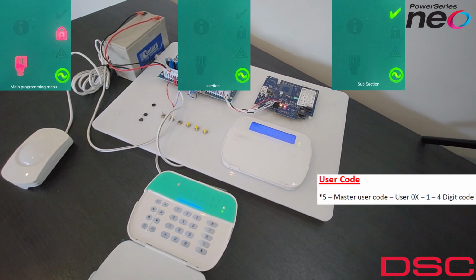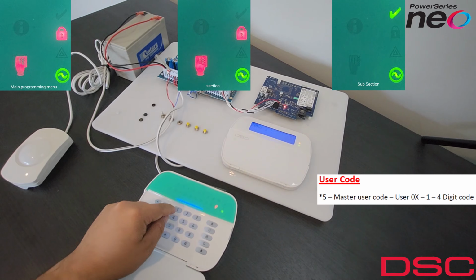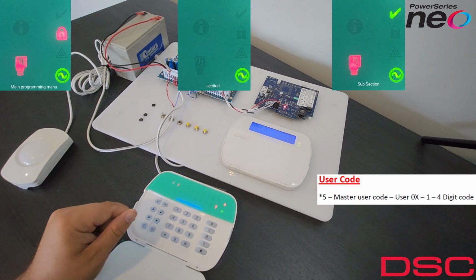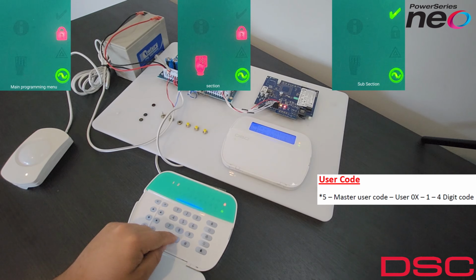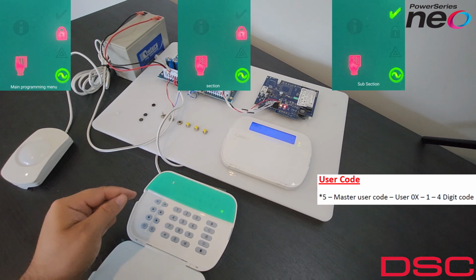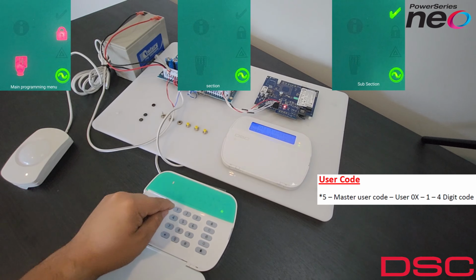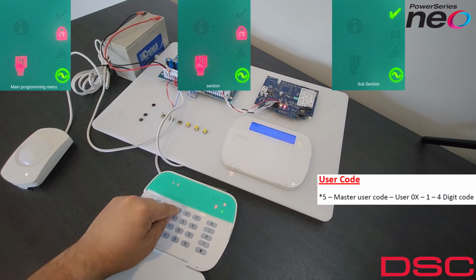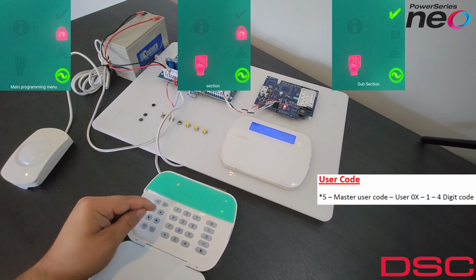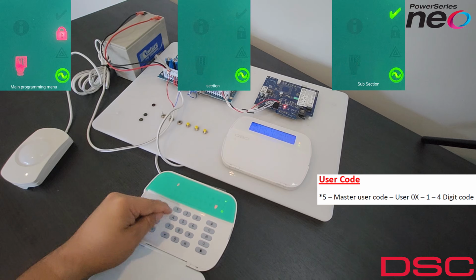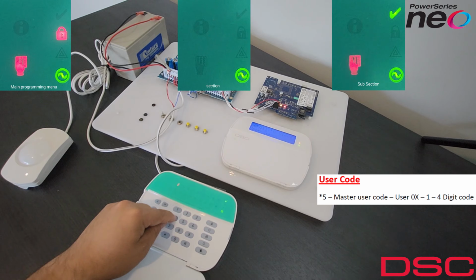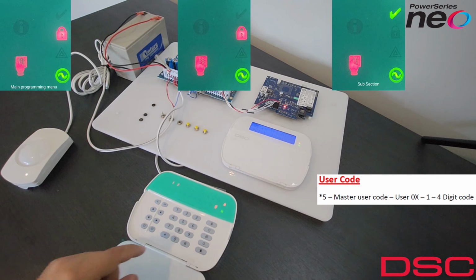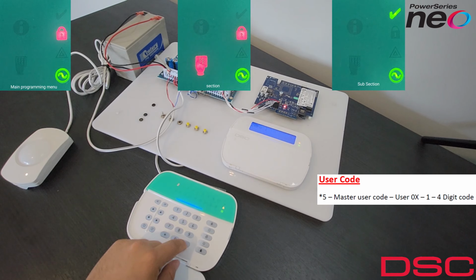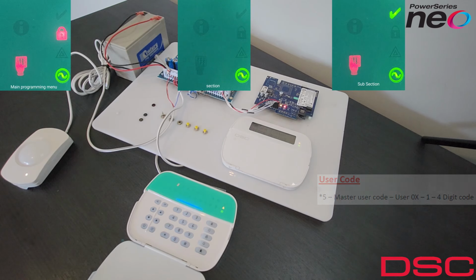Okay, from here we're quickly just going to go through and set a user code. So what you want to do is go *5, then you want to put in your master user code, then you want to put in the user that you want. So for me I'm just going to go 02 for user 2. Then you want to select the first option to enter a code, which will be number 1. And then you want to put in your code. So from here, I'll just put in 4444, 4 4s. Sweet. Then just hash out. And that user code is good to go.